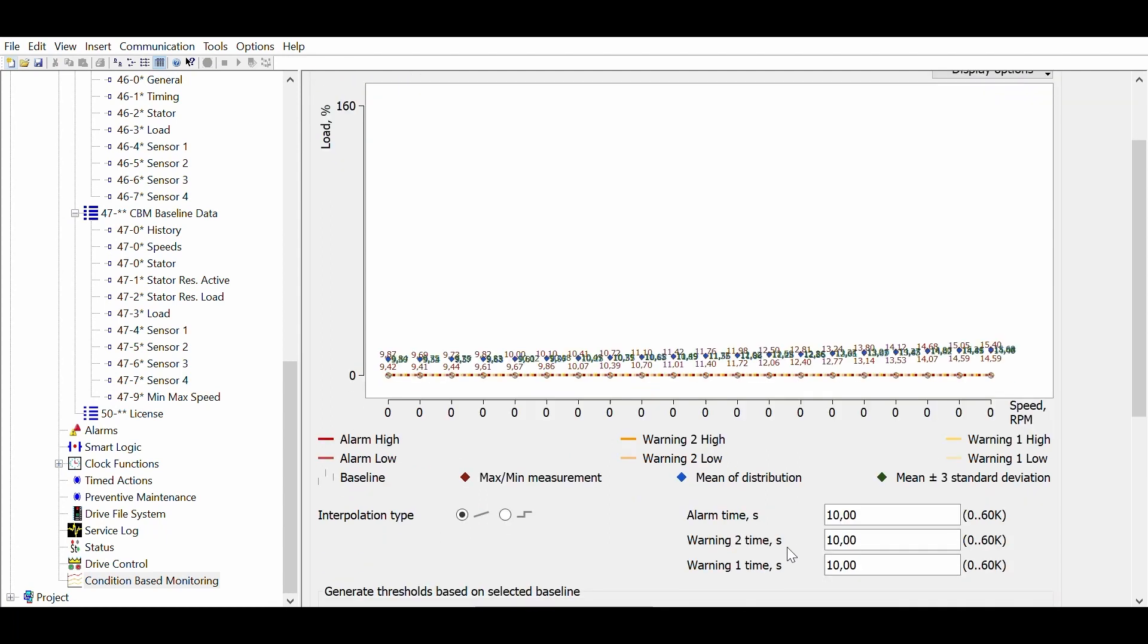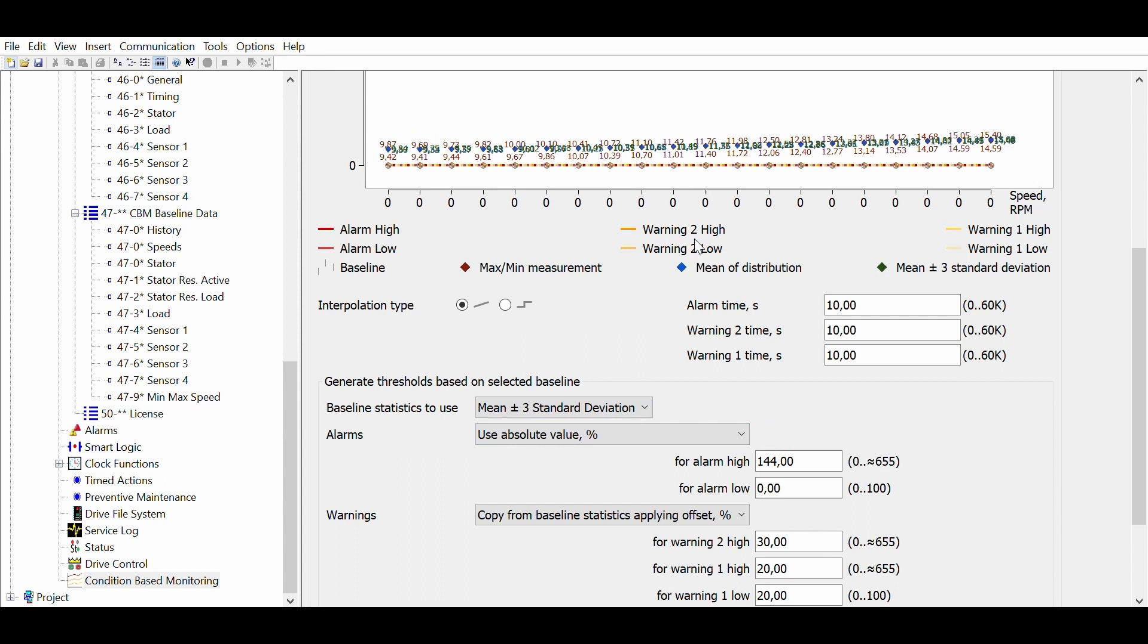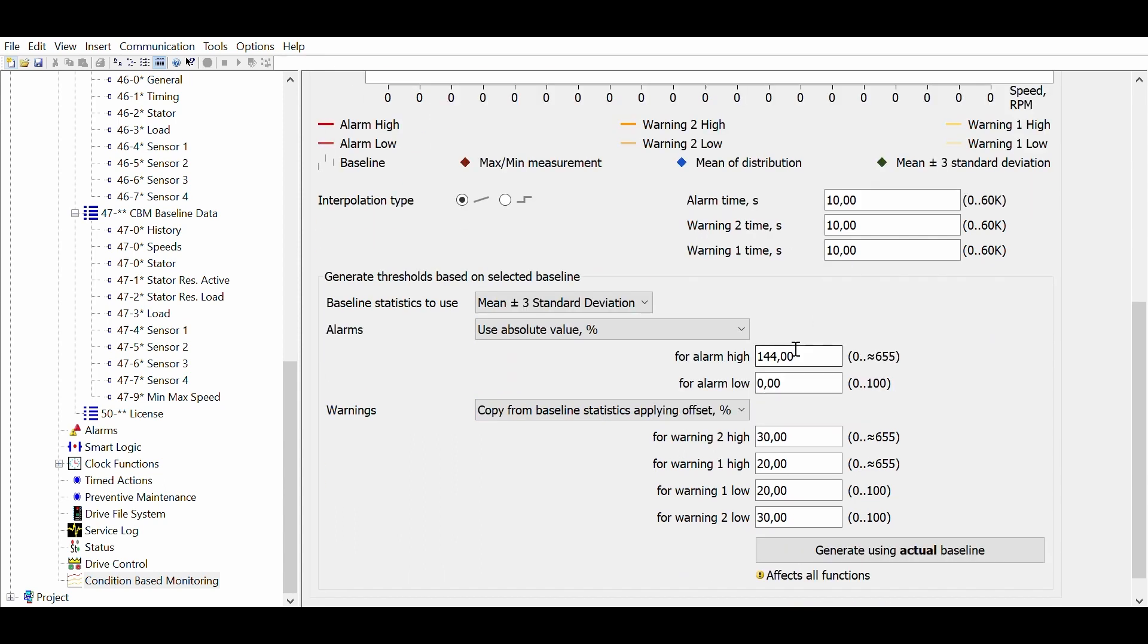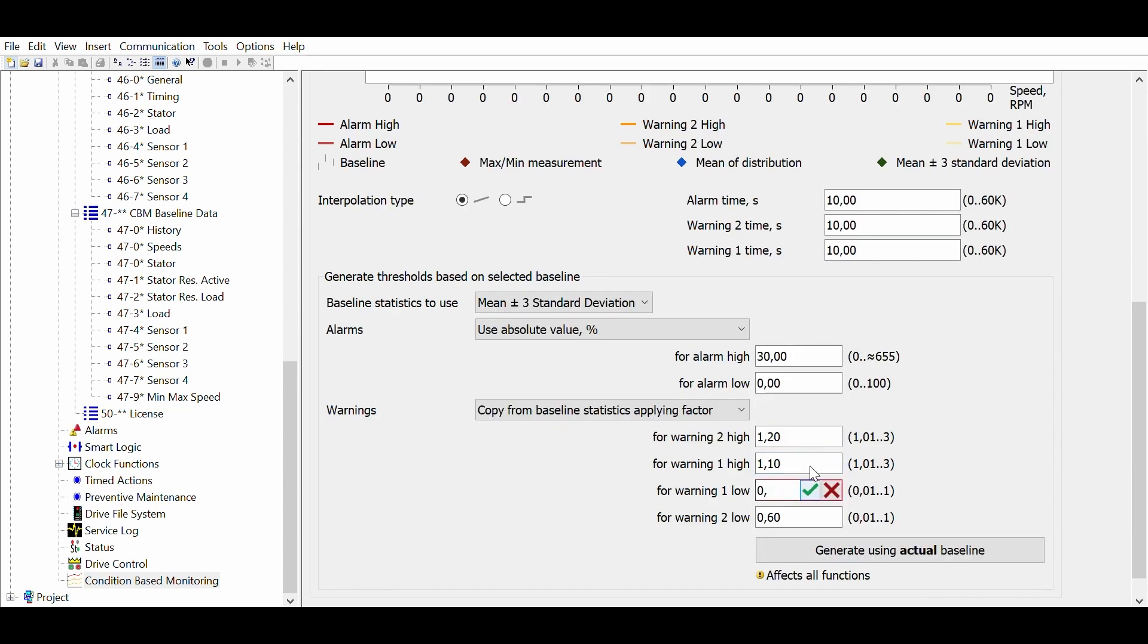For the load monitoring we will base the threshold on the mean values plus minus 3 standard deviations. For the alarm level we will set an absolute value at 30%. The warning levels will be based on the baseline values to which a factor will be applied. Load envelope has both upper and lower thresholds. We will set the upper threshold at 110 and 120% of the baseline and the lower thresholds at 90 and 80% of the baseline.